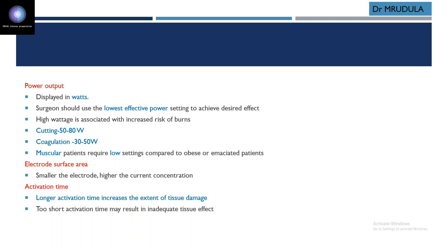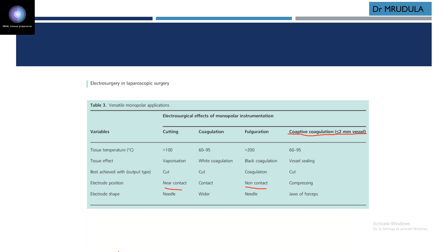Where there is contact, where there is non-contact, and what is coaptive. One more thing: coaptive coagulation is used for vessels less than 2 mm. Here you compress the tissue between the two electrodes to stop the blood flow completely. Then there will be direct wall-to-wall attachment, resulting in coaptive coagulation. The mechanism is that blood acts as a conductor of heat and decreases the effect. If you compress the vessel correctly and stop the blood flow, it results in coaptive coagulation.